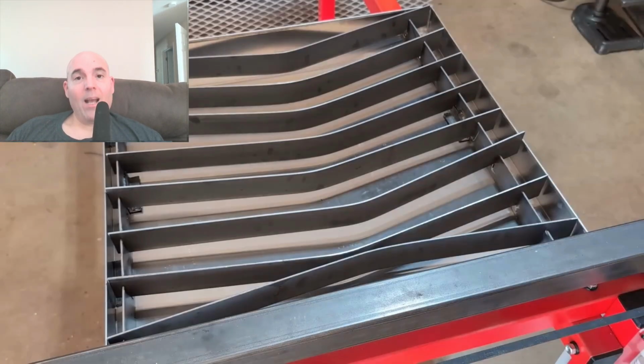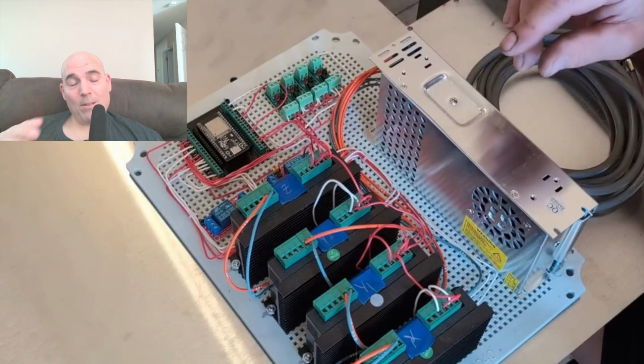That being said, there's another key point I didn't discuss early in the video. We're going to talk about it real quick now, and that is the fact that he's using a plastic electronics enclosure. Plastic is an insulator. It cannot be grounded. If it can't be grounded, you are going to be SOL when, once again, we have to make sure that enclosure is grounded so that our electronics are protected.